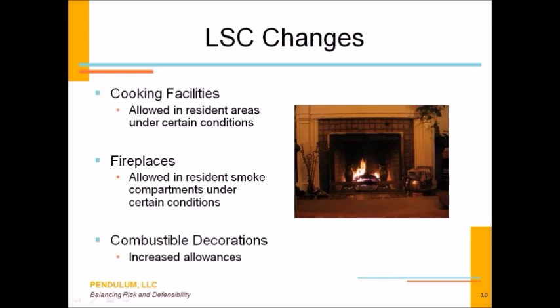You're not going to be able to do any kind of heavy cooking or frying in that open kitchen that comes off the corridor within that smoke compartment that is fully protected with a sprinkler system, fire protection system, you know, smoke detectors, etc. But it can only serve a population of 30 residents or fewer. Get into section 18 or 19 of NFPA 101. Of course, 18 is for new healthcare facilities, and Chapter 19 is for existing healthcare facilities. The information that you need to know about cooking facilities within a patient care area are clearly defined in there.